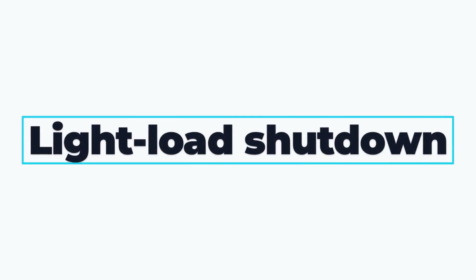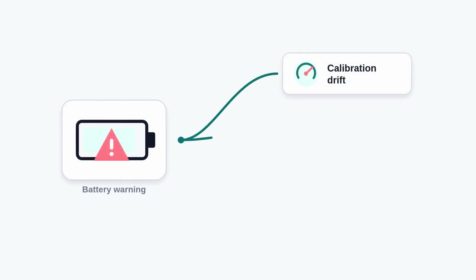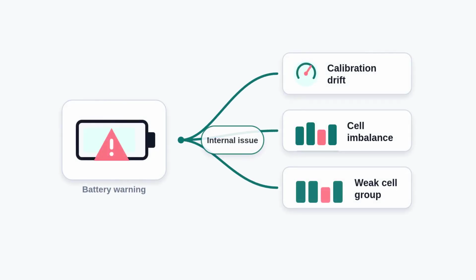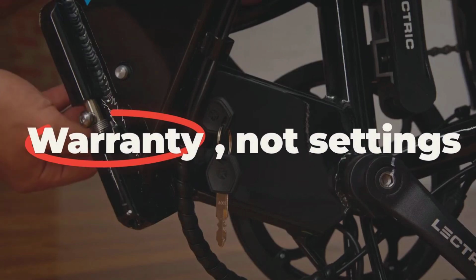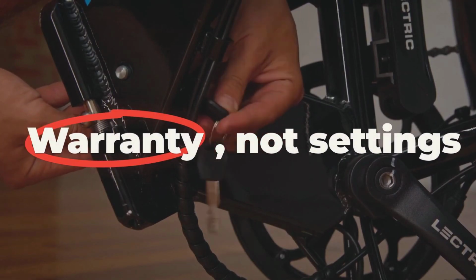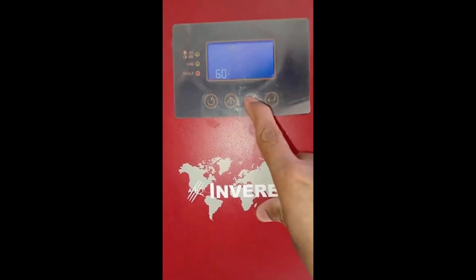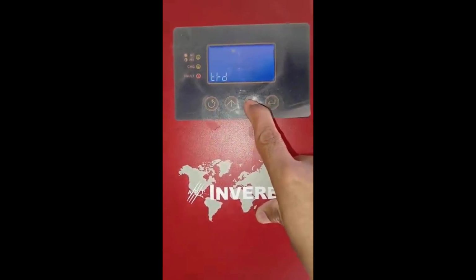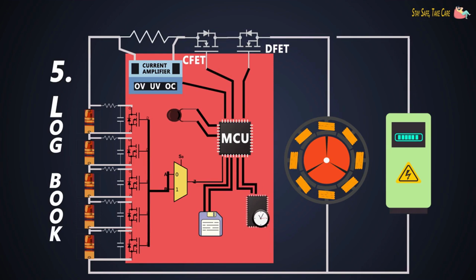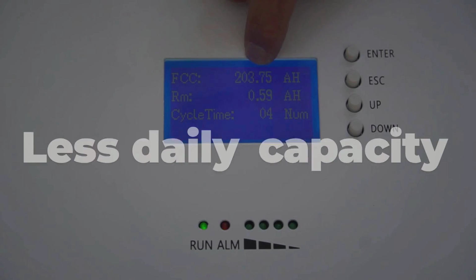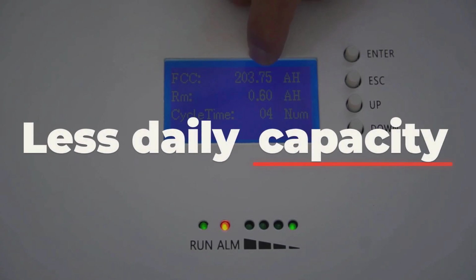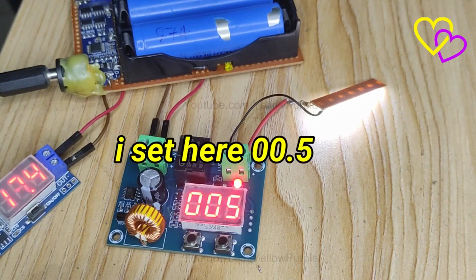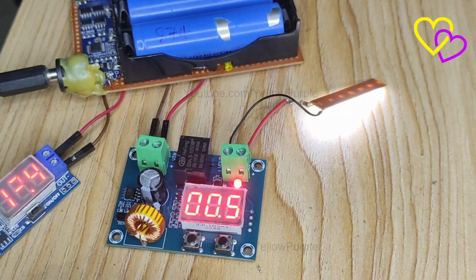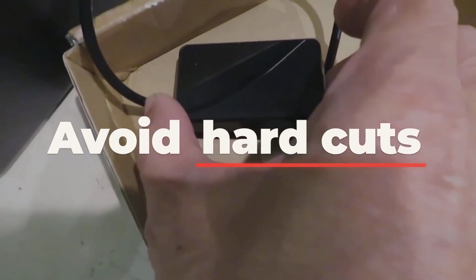If shutdown happens at light load, that is a different problem entirely. That pattern points toward calibration drift, cell imbalance, or a genuinely weak cell group. Raising the floor helps, but it does not fix bad cells. That is a warranty conversation, not a settings conversation. The trade-off is real and worth saying plainly. A higher reserve floor means more stability, less stress on the cells, and longer usable life over years. It also means less capacity available on any given day. A lower floor looks like more capacity right up until the BMS hard cuts the system anyway. And that hard cut is exactly what you were trying to avoid.